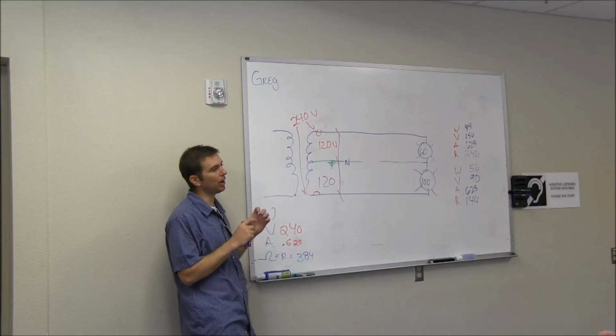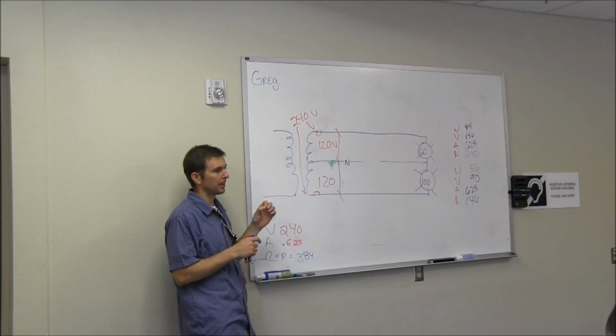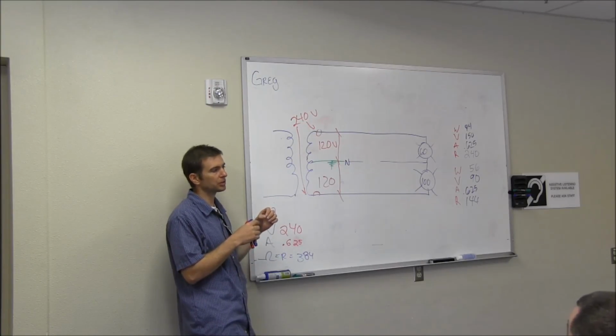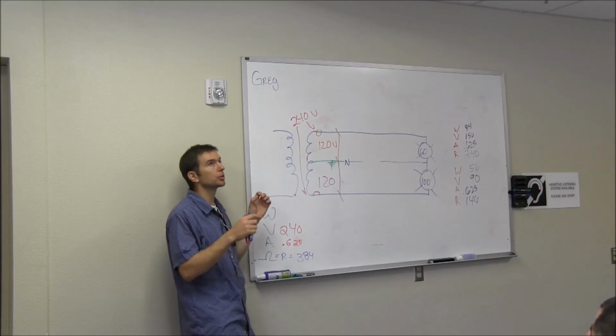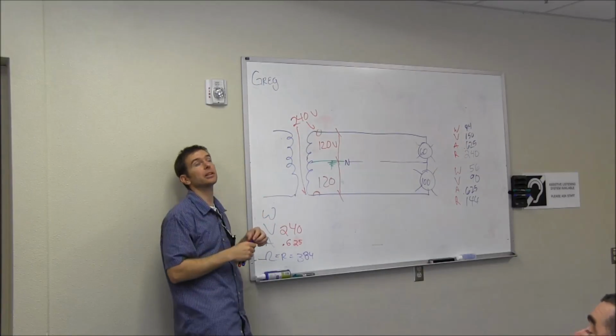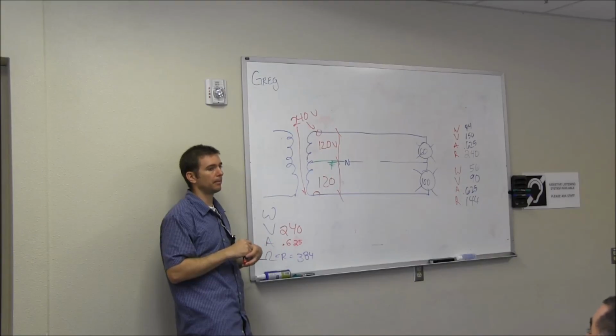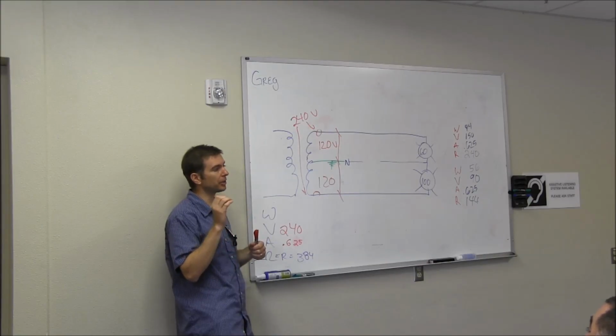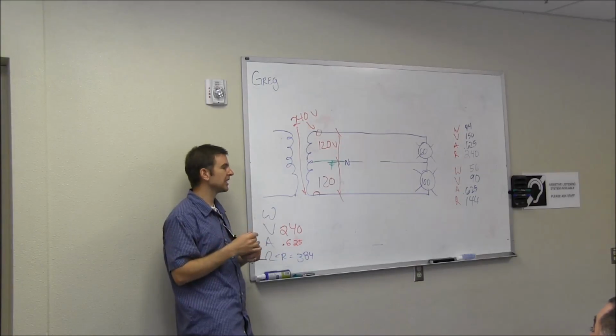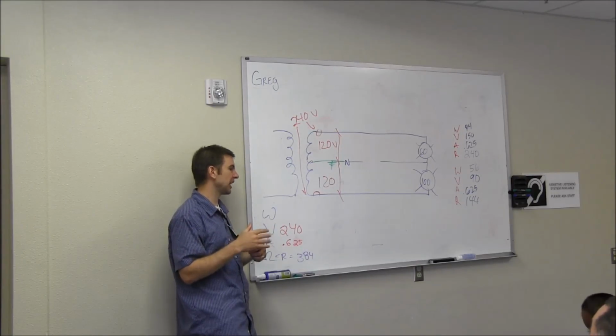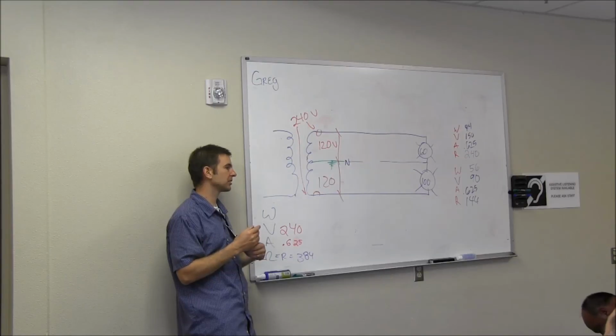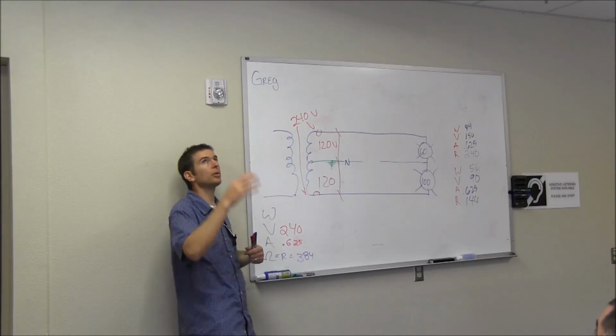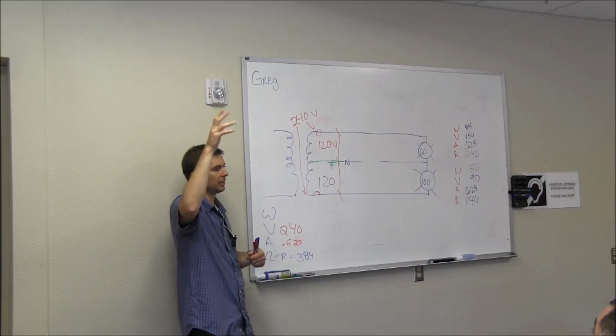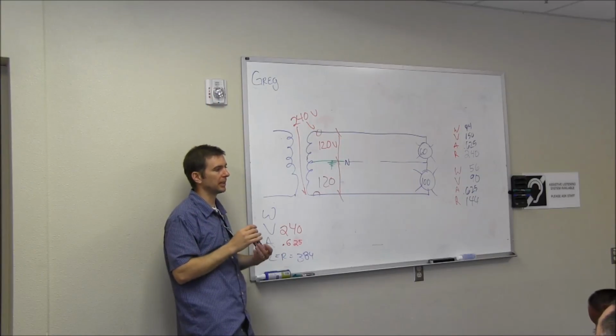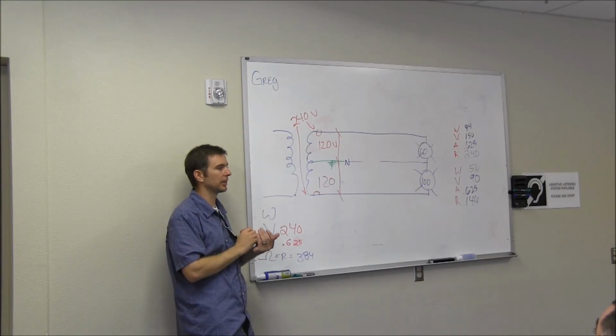If it's a T12 - the 12 stands for eighths of an inch, so it's basically an inch and a half tube - I don't know what these are, could be LED for all I know. But if the T12 is a bigger lamp and the T8s are smaller, then if it's a T12, there's a 50% chance you have magnetic ballast versus electronic. You wouldn't know without opening it up, and you'll be able to see whether it's electronic or magnetic - it'll say on there it's electronic ballast.